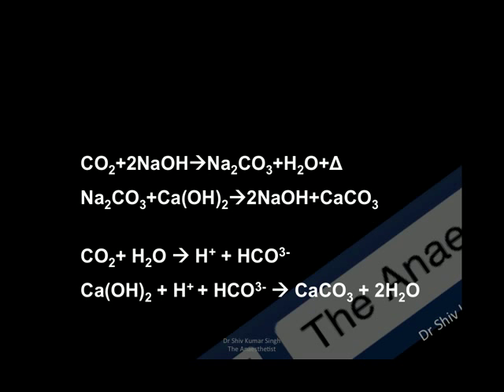This reaction is also important for the humidification and heating up of the gases. Carbon dioxide also reacts with water to produce hydrogen ions and bicarbonate, and it is this acid that changes the color of the indicator. Calcium hydroxide can also react with the hydrogen ions and bicarbonate ions to produce calcium carbonate and more water.